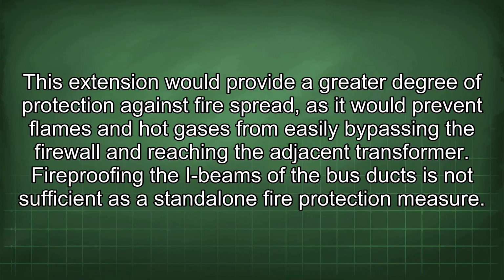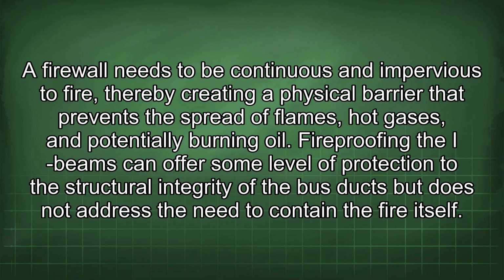Fireproofing the I-beams of the bus ducts is not sufficient as a standalone fire protection measure. A firewall needs to be continuous and impervious to fire, thereby creating a physical barrier that prevents the spread of flames, hot gases, and potentially burning oil. Fireproofing the I-beams can offer some level of protection to the structural integrity of the bus ducts, but does not address the need to contain the fire itself.